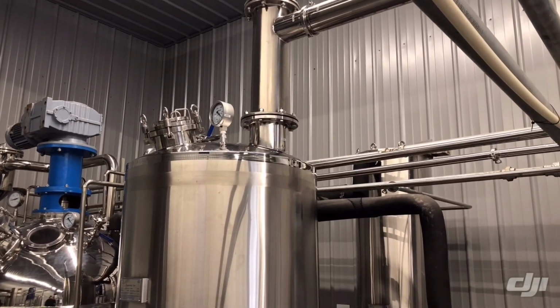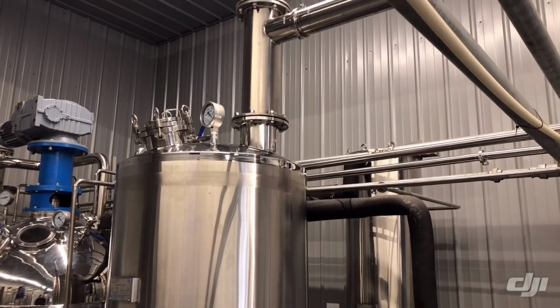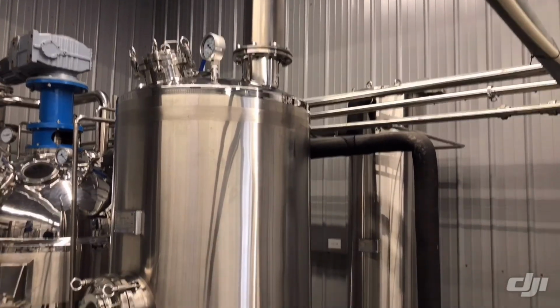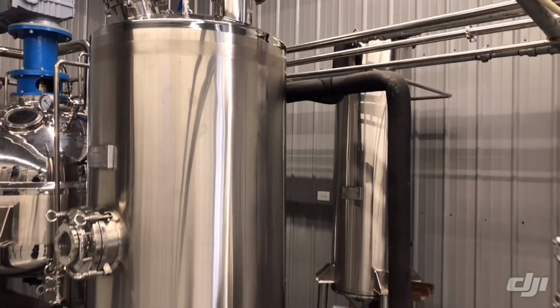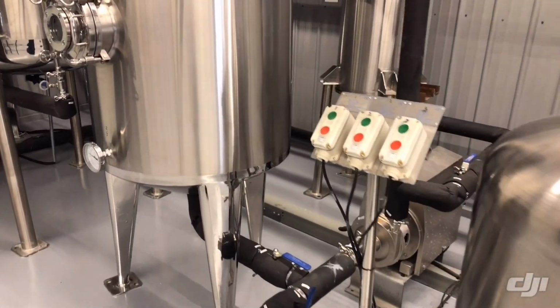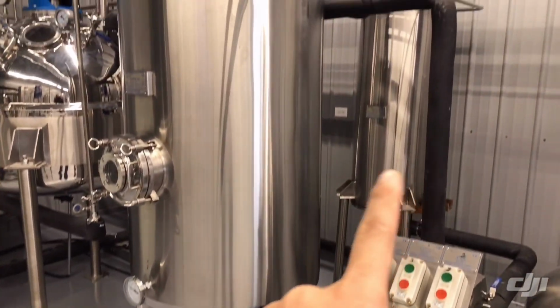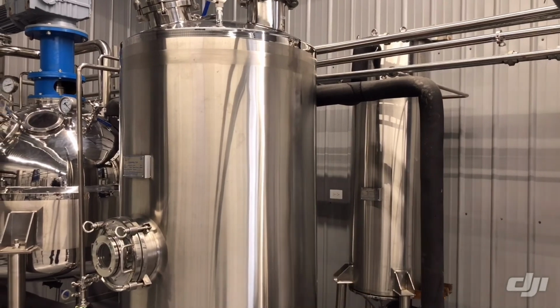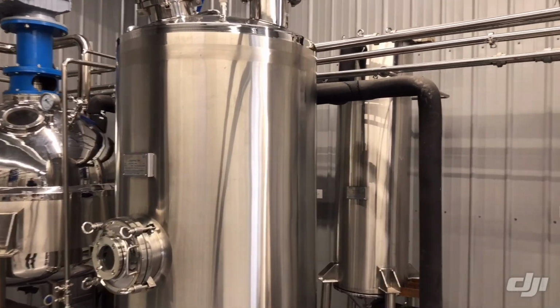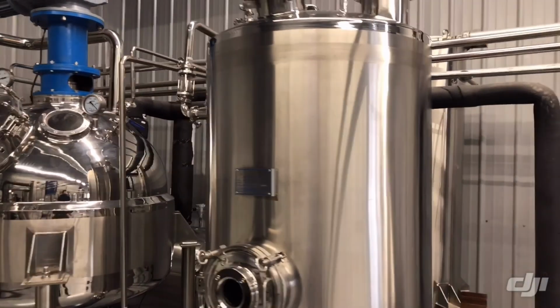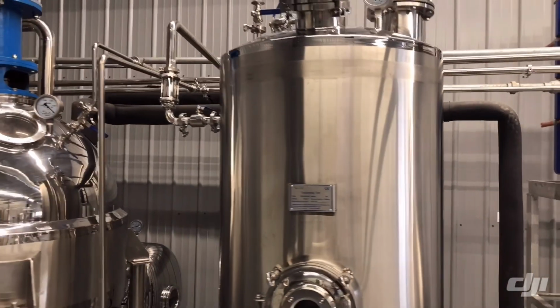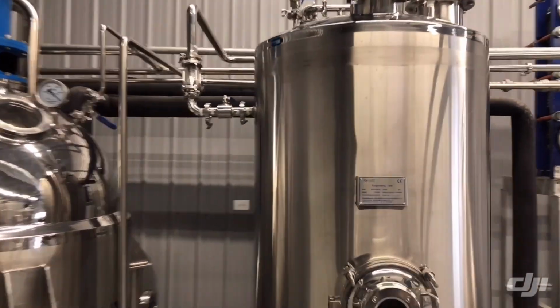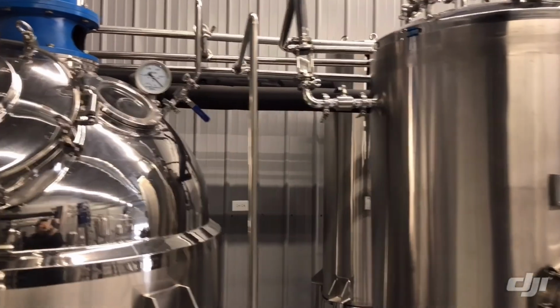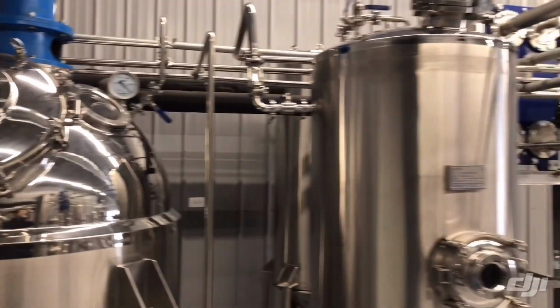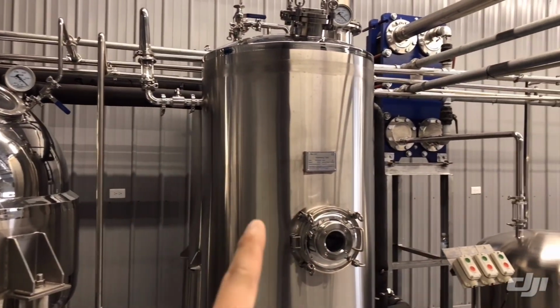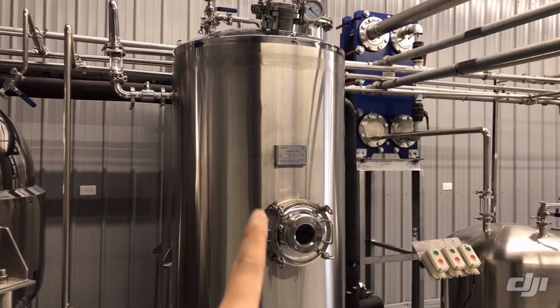On our left we have a set of what we call a falling film evaporator. This falling film evaporator claims it can recover about 500 liters of ethanol, around 130 gallons per hour. All the filtered liquid comes inside, and all the ethanol with a low boiling temperature boils off and becomes vapor, transferring into the heat exchanger and condensing in the storage tank.